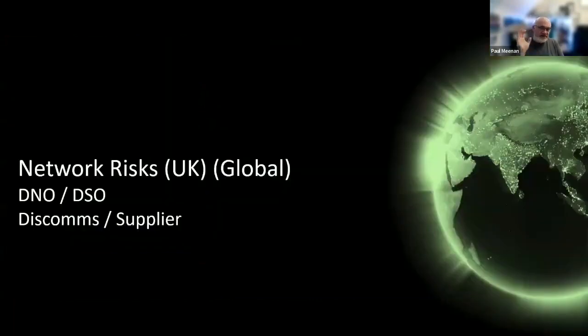So getting back to those images where we had that earth current, what could be wrong? What hidden mystery have we found now? The hidden mysteries we've got is the network risks, or what we call in England the DNO, distribution network operator, or the distribution system operator. I believe in India they're called the discoms or supplier. Again, feel free at the end to kick me if I am incorrect.